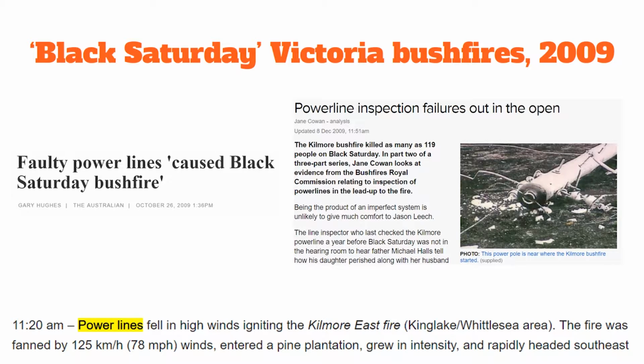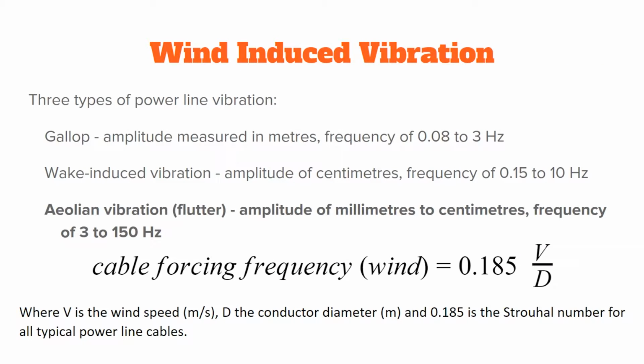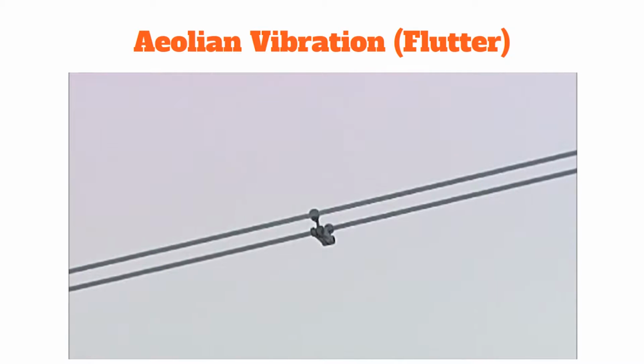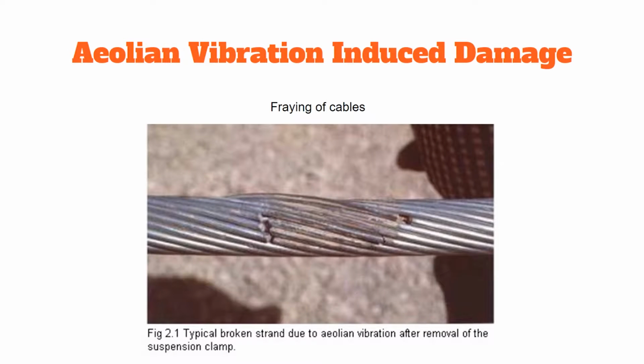High winds generated by storms or cyclones are a major contributor to the vibration. Therefore, it is important to control the vibrational behavior of power lines in the uncontrollable environment. The type of vibration that causes the most damage is Aeolian vibration. Aeolian vibration is caused by vortex shedding. Under moderate wind speed, von Karman vortex shedding will induce vertical vibrations at frequencies depending on the Strouhal relationship. Aeolian vibration's high frequency causes accelerated fatigue damage to the supports on the towers, as well as fraying the cables themselves. Frayed cables eventually snap at the supports, which results in fallen power lines.